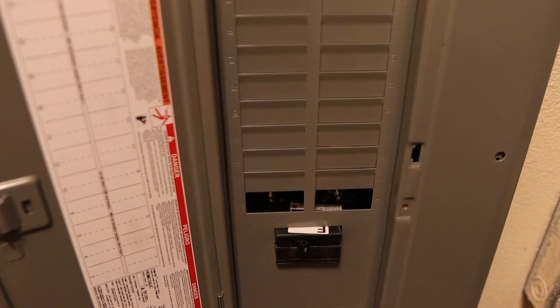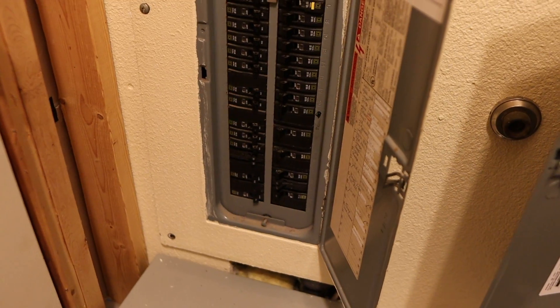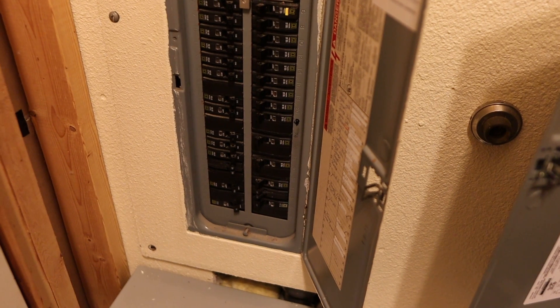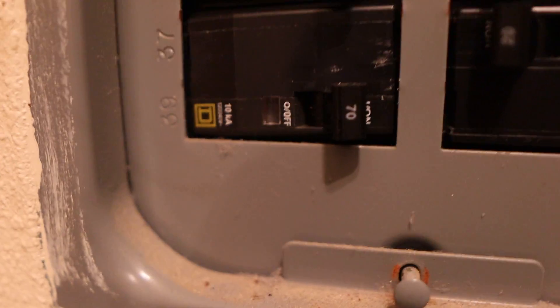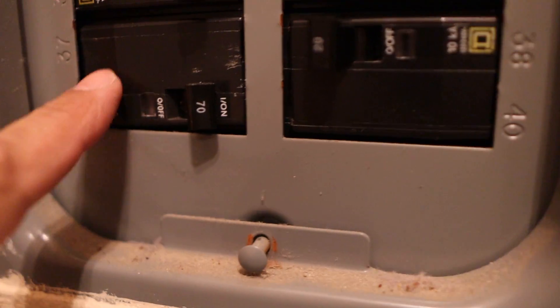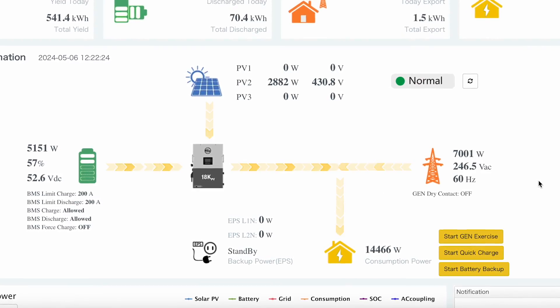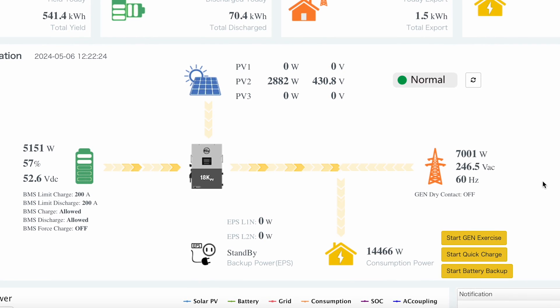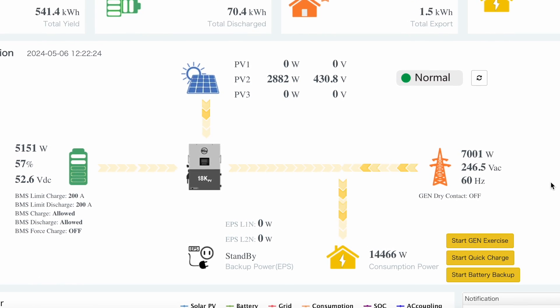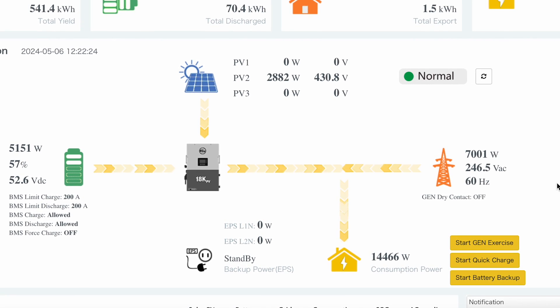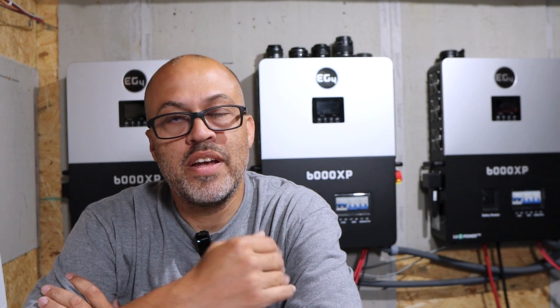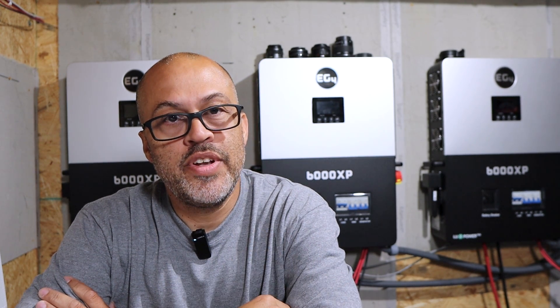But some of you guys are wondering, since it's a partial backup, basically I put a subpanel in that I'm going to power loads from. But it can also feed back to the main panel, your grid input on the inverter. It'll feed back to that line, any extra solar that's coming in, and power your loads in the main panel without exporting it and selling it back to your power company. Unless you have it set up that way. If you have an agreement with them, of course you can do that. But we don't have ours set up that way. So it's just going back to the panel, have the CTs on the panel. That's going to stop that from going back to the grid. And some people are wondering about my settings. So that's what we're going to do in this video.